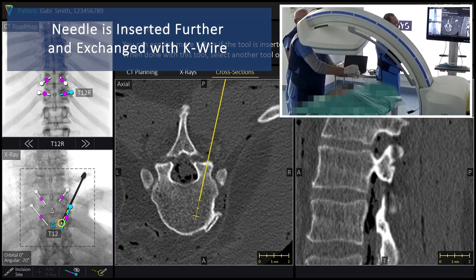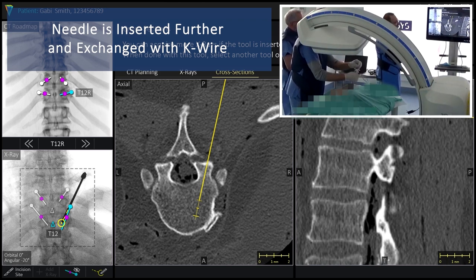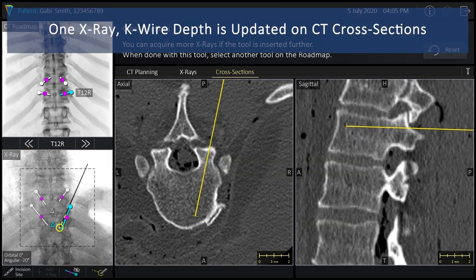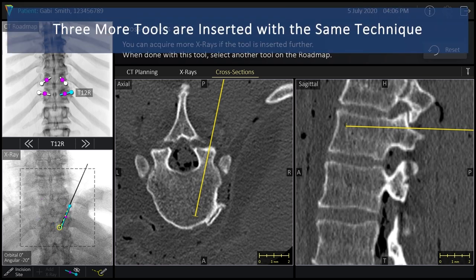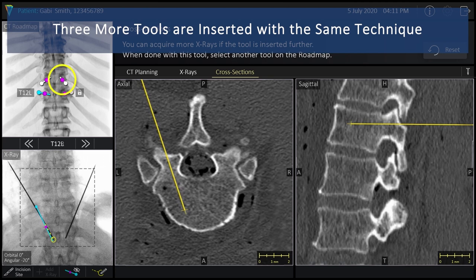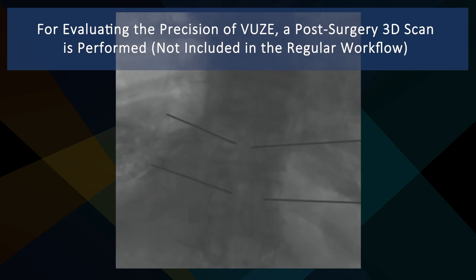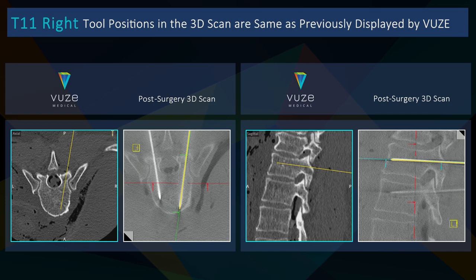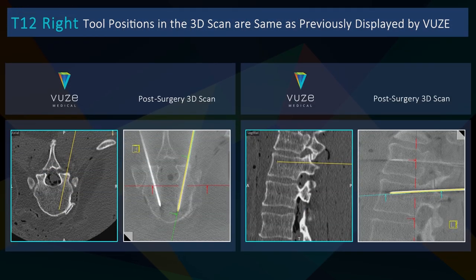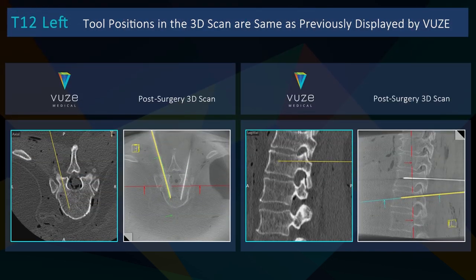Then we do the tool exchange — K-wires, pedicle screws, etc. — and the same process is repeated for the other three pedicles. In all of our cadaveric workshops, as well as in our clinical trial, we do a 3D spin to compare the synthetic images VUZE has generated to the real 3D situation. We've done many hundreds of cadaveric insertions and 14 clinical patients. That data is also provided to the FDA, and the comparisons are always extremely accurate.